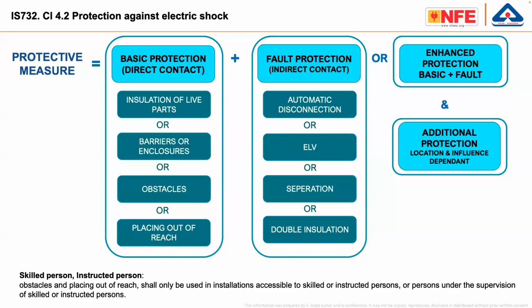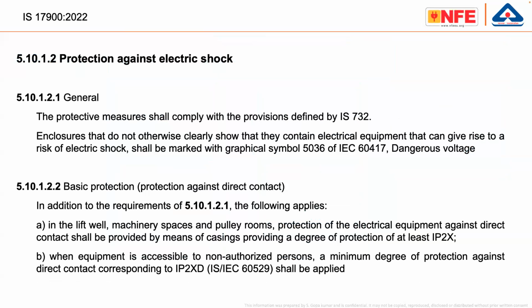Say, for example, IS 17900, the new lift standard, clause 5.10.1.2, talks about protection against electric shock. So very simple. The first line says a protective measure shall comply with the provisions of IS 732. The previous slide which I have shown you is from IS 732. So the same thing has to be followed here.